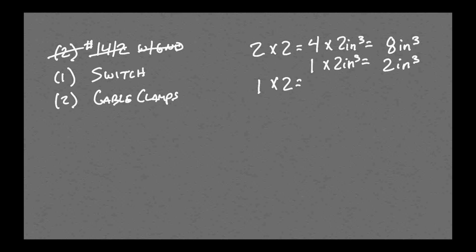So now I have 2 conductors because I have 1 switch times 2 conductors. The size of conductor that's connected to that switch is number 14. So it's worth 2 cubic inch. So that's 4 cubic inch. So my switch is taken care of.